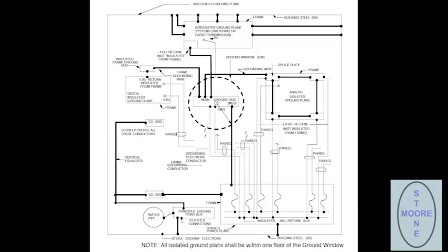We isolate it from anything, any building steel, cable racks or anything, for at least 2 inches above it and on all sides of it, and we'll call that the isolated ground plane. Is that why you see in action movies guys can swing from the power lines, because you can touch it? Yeah, as long as you're touching only it. Things get real different when there's something else involved, when there's a current path. And the higher the voltage, the more likely it is to happen.